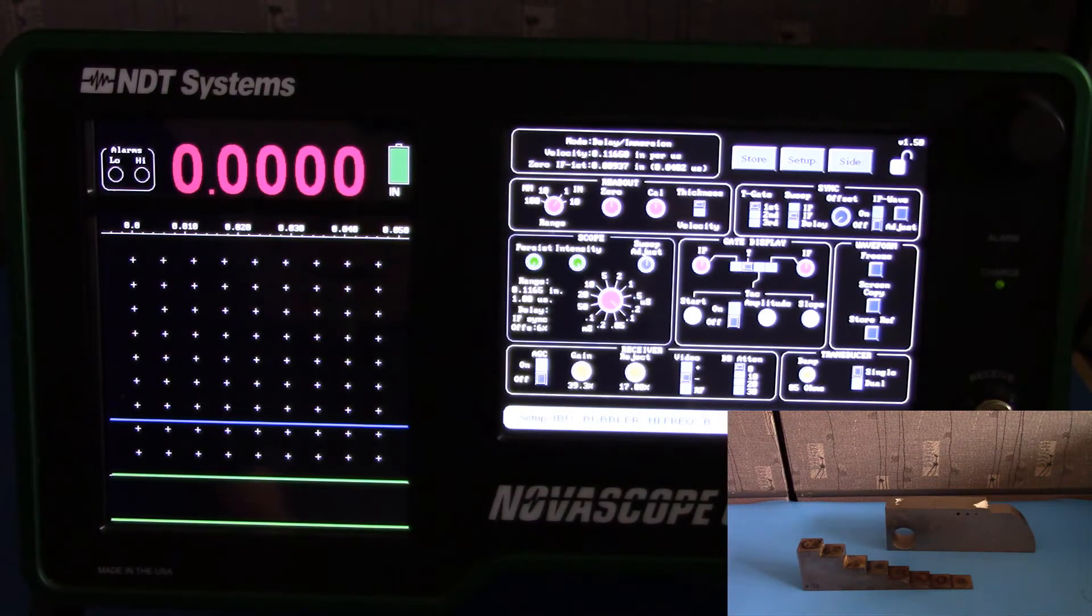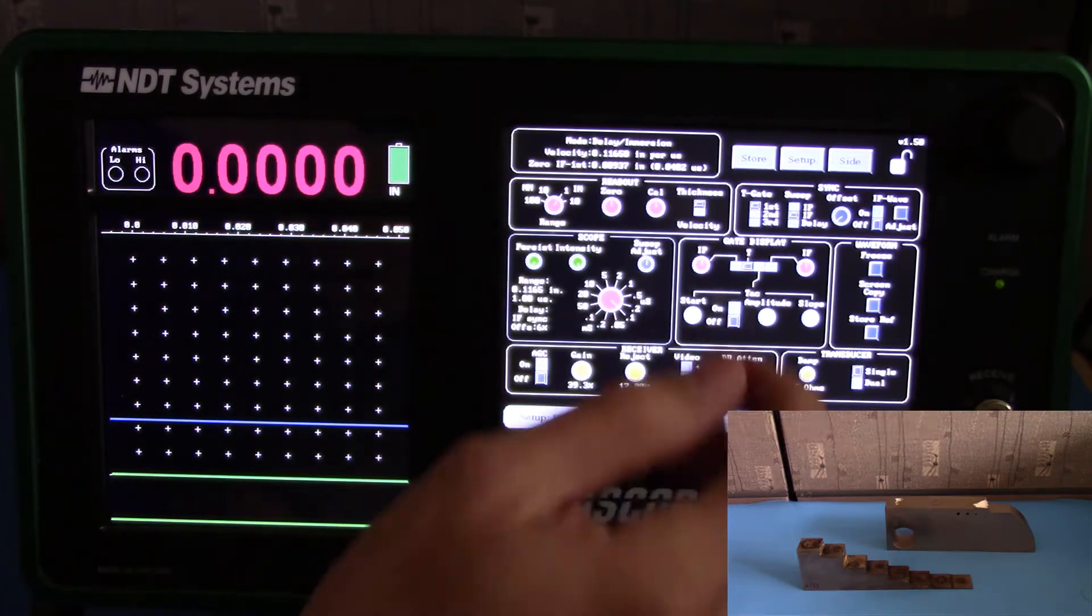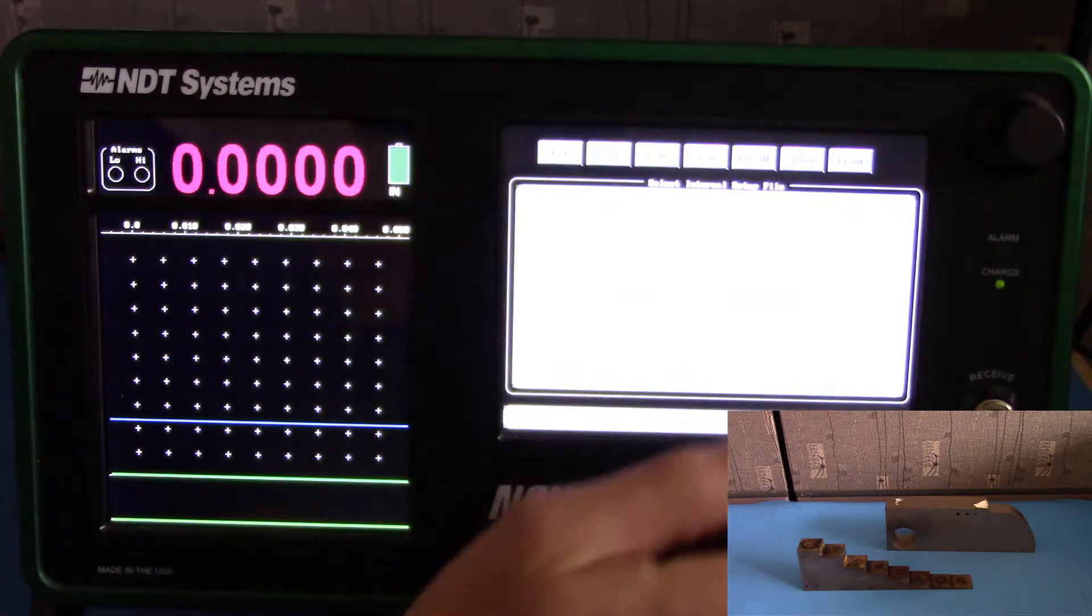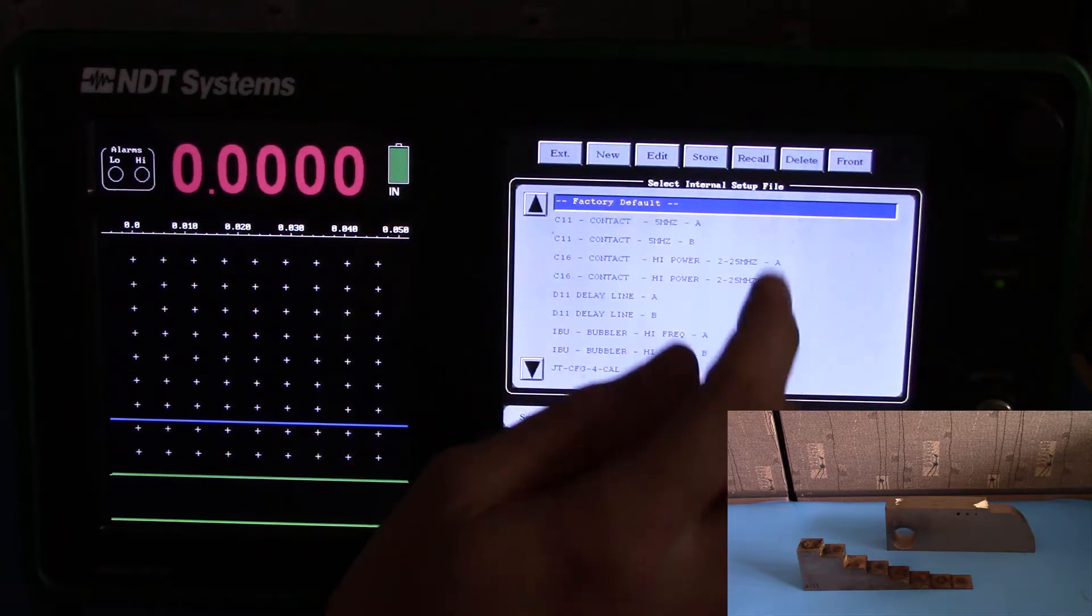To begin calibrating the NovaScope for contact probes, first we'll need to verify that the settings on the NovaScope are at the factory default. To do this, go to the Setup menu located on the top of the screen, navigate to Factory Default, and hit Recall.